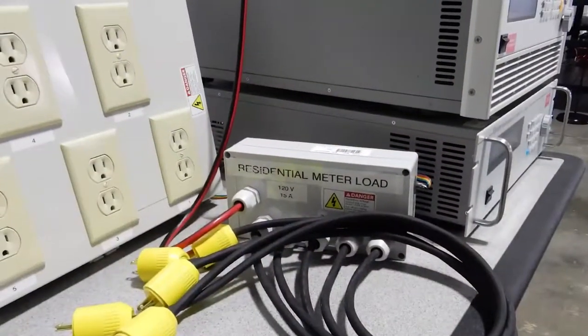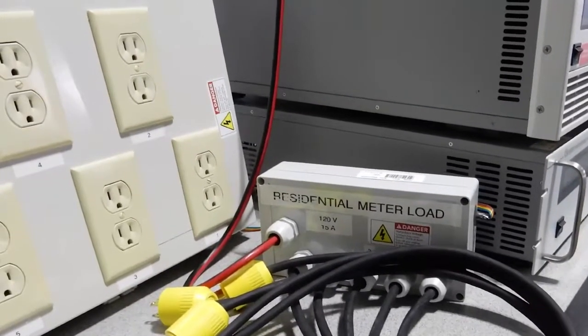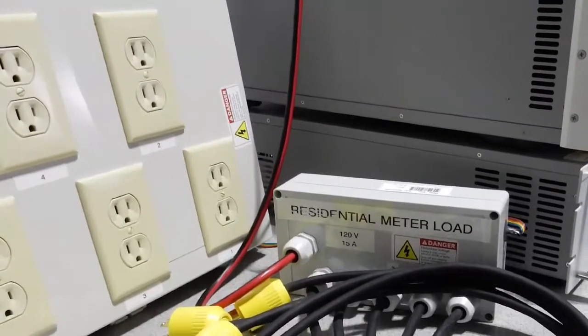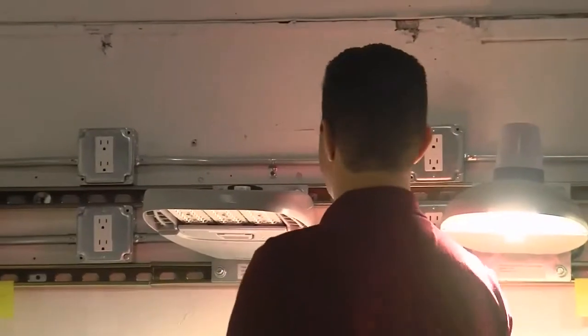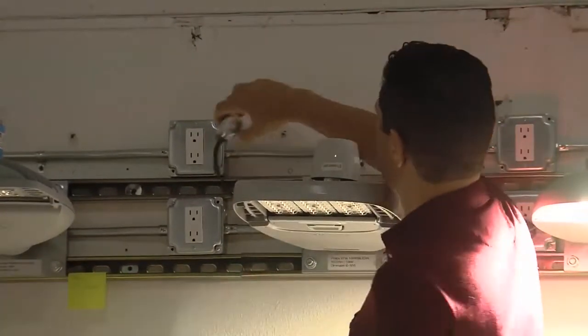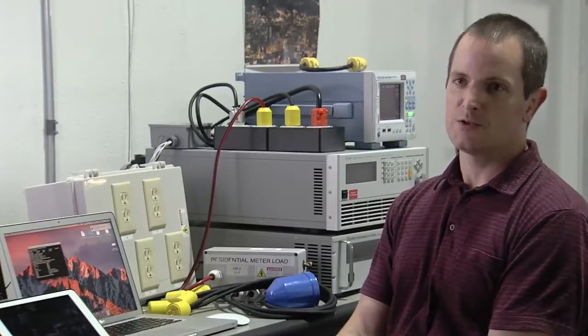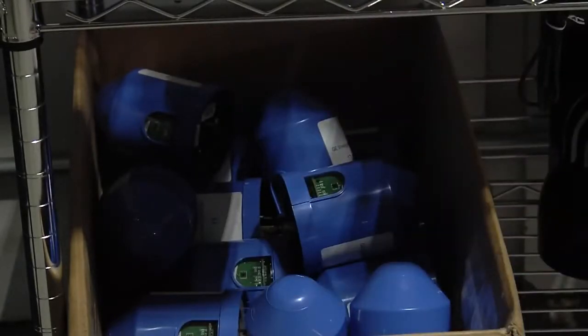To vet the accuracy of a test apparatus that we've put together, we started looking at connected outlets to see how these various products perform in terms of energy reporting accuracy. One area of study in connected streetlight systems is the energy reporting accuracy of these connected streetlight systems. A first technology that we're investigating is connected streetlight control nodes and looking at their accuracy of energy reporting.